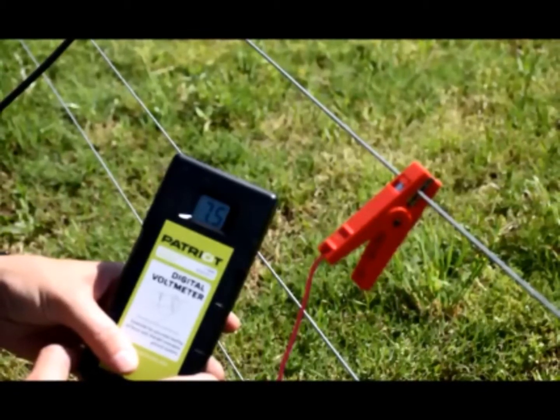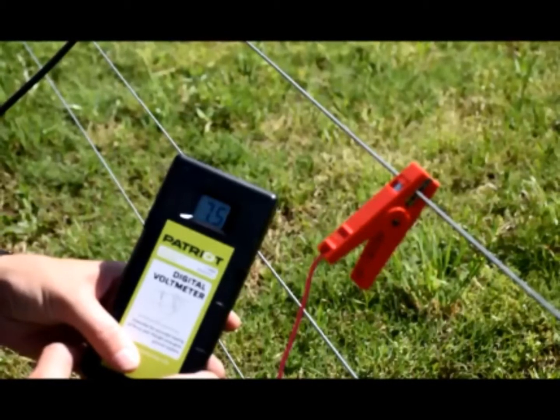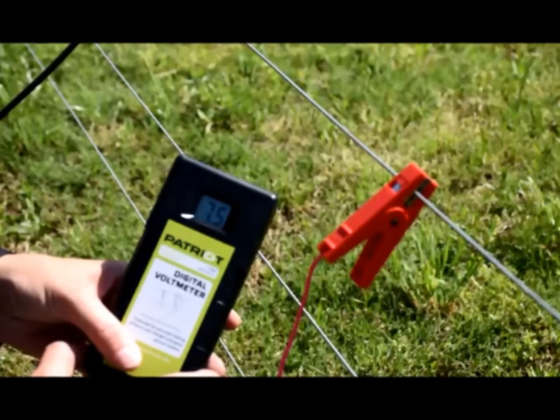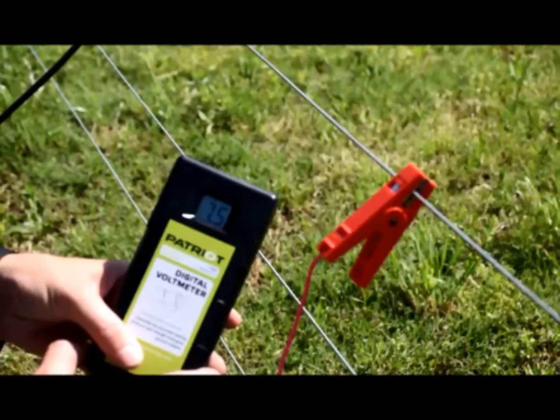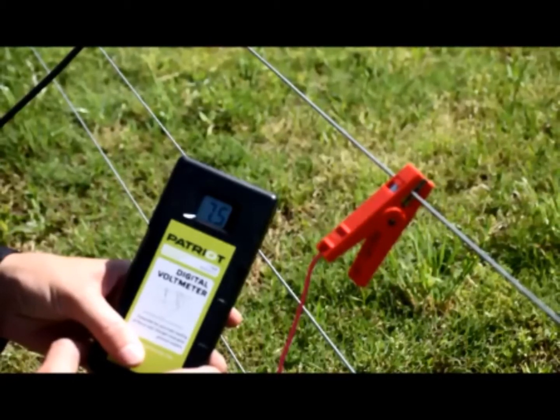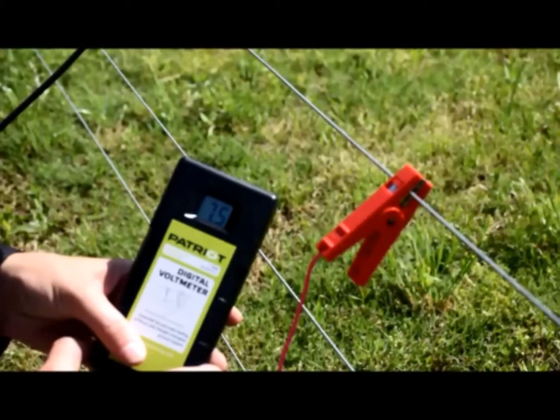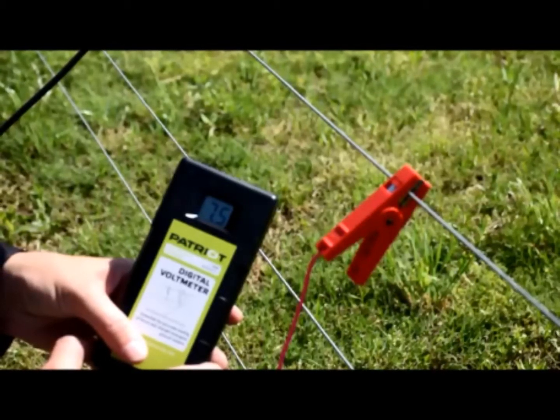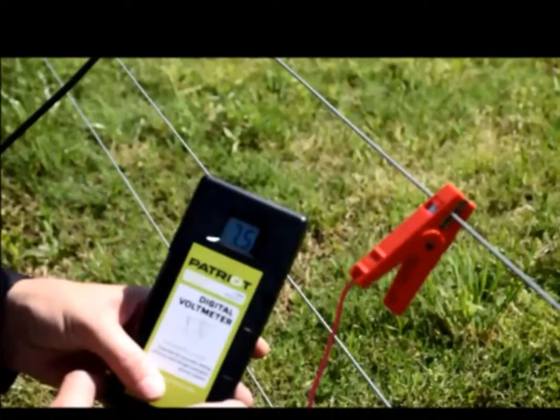For PE model Energizers, if you have a reading of 2.0 or higher, your Energizer is performing fine and your installation is complete. If the reading is 1.9 or lower, please refer to the troubleshooting page in the Patriot brochure.